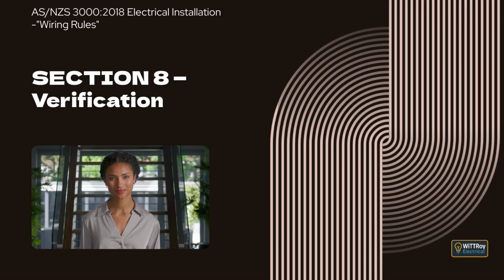Clause 8.3.7.2 Results. This clause explains that testing must show that all active, neutral, and protective earthing conductors are correctly connected to the corresponding terminals of electrical equipment. It confirms that there is no dangerous transposition of conductors, that switches and protective devices operate in the correct conductors, that phase sequence is consistent where required, that no protective earthing conductor is connected in parallel with the neutral conductor, that there are no short circuits between conductors, and that there are no unintended interconnections between different circuits. It also clarifies that any MEN or ESA connection is not regarded as a short circuit.